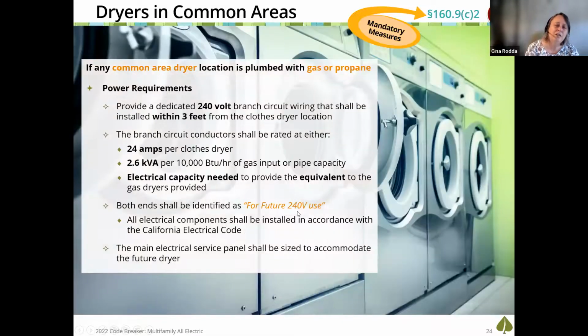Now this one's unique. This is if you want to put in gas dryers or the gas infrastructure for a central or common laundry facility, whether it be within the building or a separate building. I don't care if it's a laundry building. I don't care if it's laundry facilities within the multifamily building. If it is serving more than one dwelling unit and it's not systems within the dwelling unit, now I look at what's the capacity of that laundry facility.